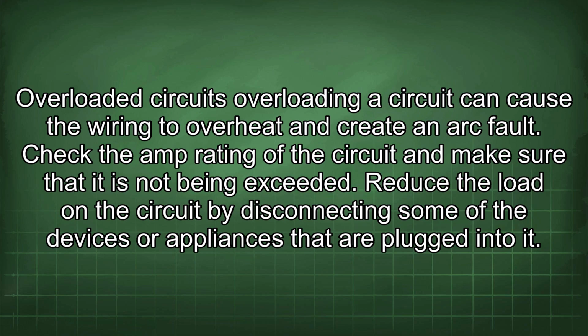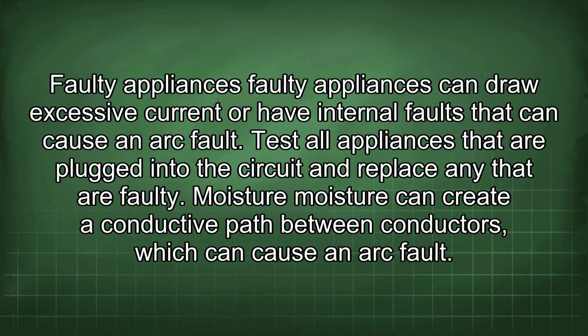Overloaded circuits. Overloading a circuit can cause the wiring to overheat and create an arc fault. Check the amp rating of the circuit and make sure that it is not being exceeded. Reduce the load on the circuit by disconnecting some of the devices or appliances that are plugged into it. Faulty appliances. Faulty appliances can draw excessive current or have internal faults that can cause an arc fault. Test all appliances that are plugged into the circuit and replace any that are faulty.